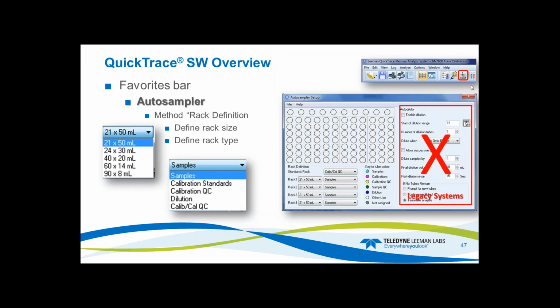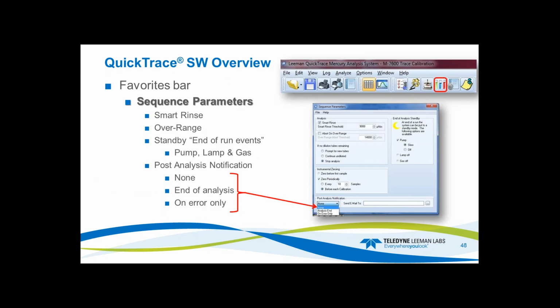Autosampler. So here's our little icon for the autosampler right up here. Trying to get my mouse, well, there it is. And here you define the rack definition. So define rack size and rack type. Under sequence parameters, this is where you set up your smart rinse, overrange, your standby routine, end of run stuff, so lamp on, gas off, that kind of stuff as well.